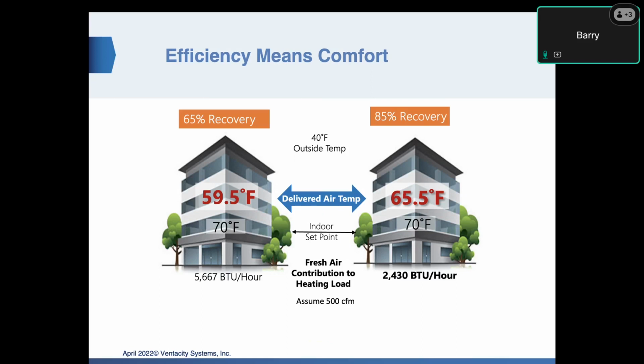From an energy perspective, that's where it really gets interesting. The amount of energy to take, in this case, 500 CFM, which would be a single classroom or a modest-sized office, from that 59.5 degrees up to 70 degrees at 65% recovery on the left, we're showing 5,667 BTUs an hour. That 20% difference in recovery efficiency translates into almost 150% difference in energy. So rather than 5,600 BTUs an hour for that classroom, say, we're looking at 2,400 BTUs an hour. So you're having to use a much smaller heating and cooling system in a building that has that very high efficiency ventilation.